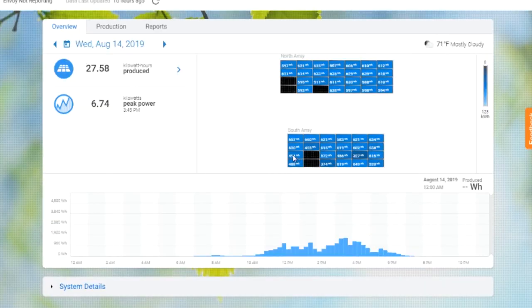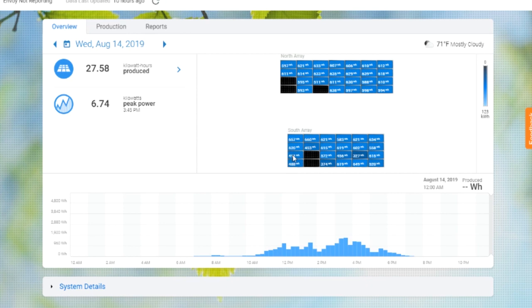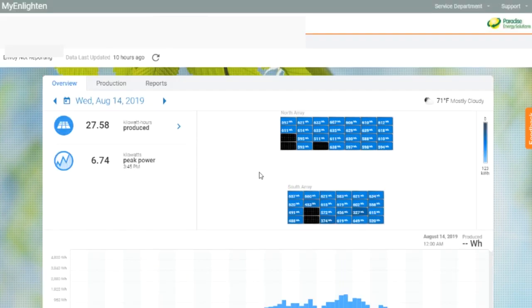If you have some panels, say, in the corner of your array that are producing less than the ones around them, one thing you may want to check for is shading. Because if there would be shading on this part of the array, these panels would obviously be producing less, and that would show up in these numbers. So if there's one spot in your array that's always producing less, you do want to check to see if you have any shading out there.